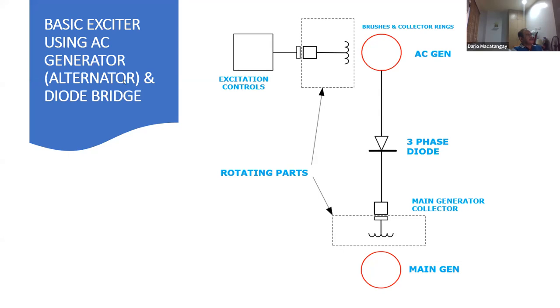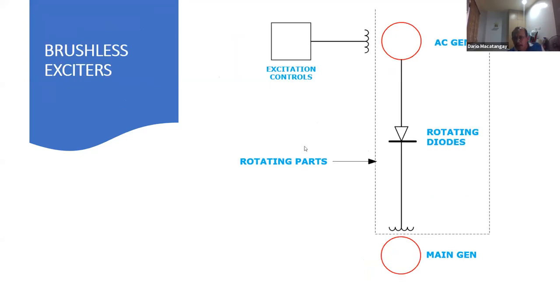So now this is an exciter using a diode bridge. Now this one here is another modification. They use a brushless exciter now. As you can see, they eliminated the brushes. When they eliminated the brushes, you need the diodes to be rotating, so it has a rotating diode with itself. The AC generator with rotating diode is feeding the DC part of the main generator. These are the rotating parts. Again, the excitation control.